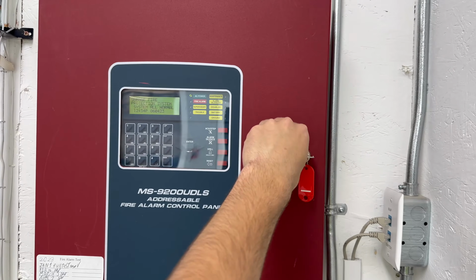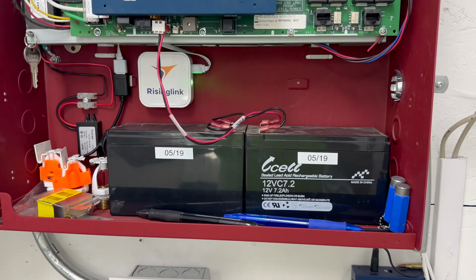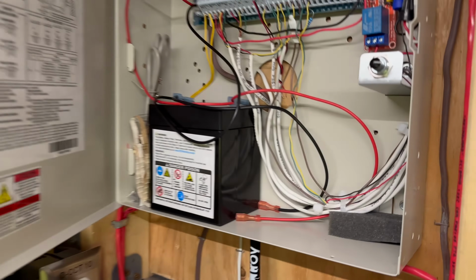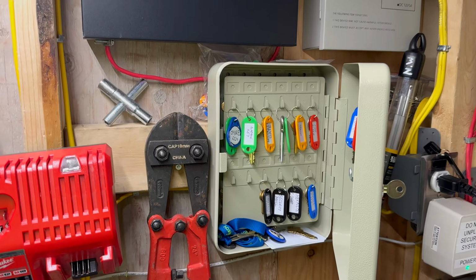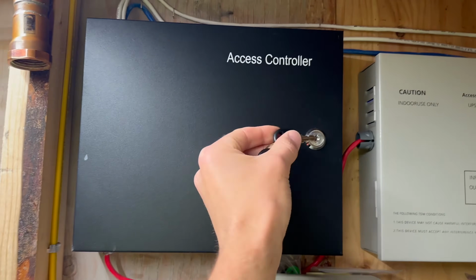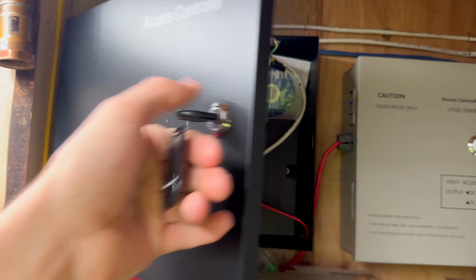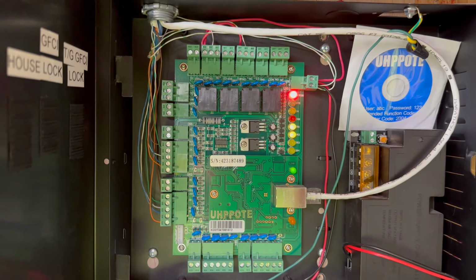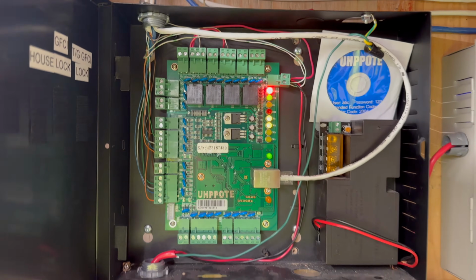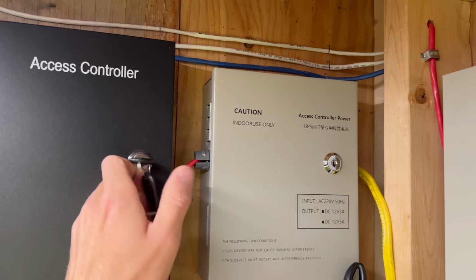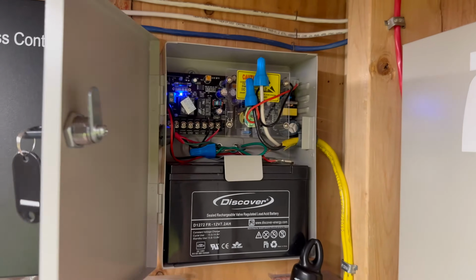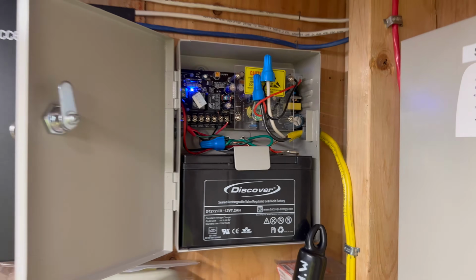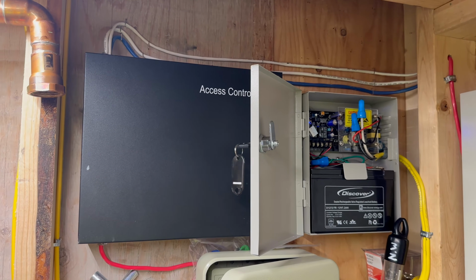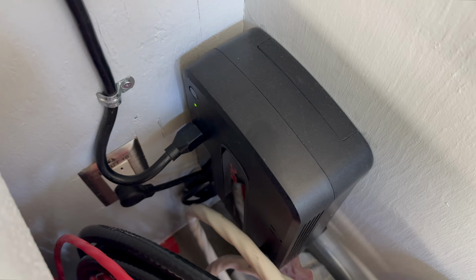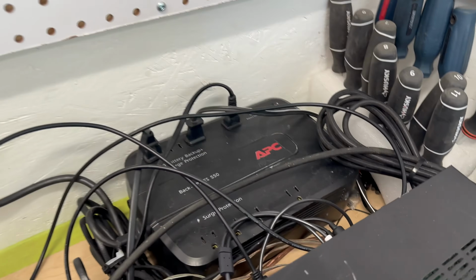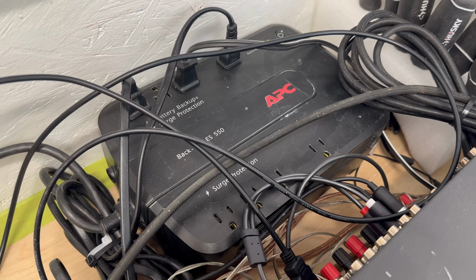The fire alarm system also has battery backup. The security system also has battery backup, as well as the door access control system, which is the fob system to let you into the building. This also has battery backup. However, it's not in this panel right here. It is in right here, a 12 volt UPS, which you can see also has a battery in here to make sure that the door access system never goes down. There is also another UPS that powers the computer, as well as another UPS in this back corner powering some equipment too.